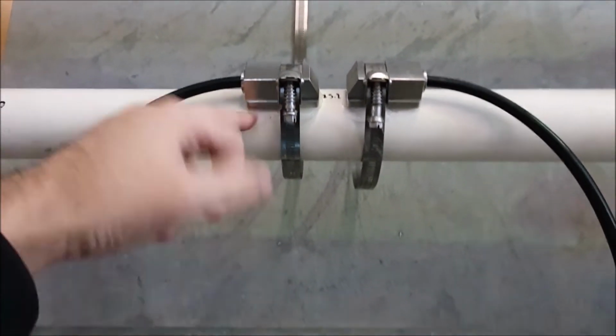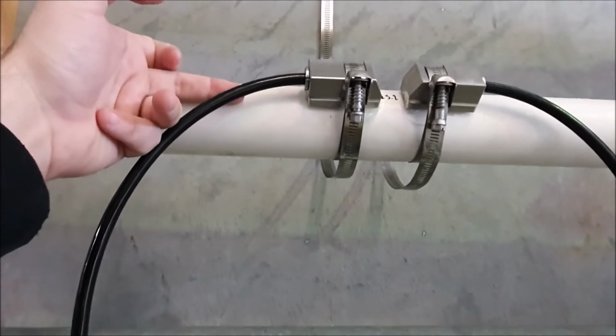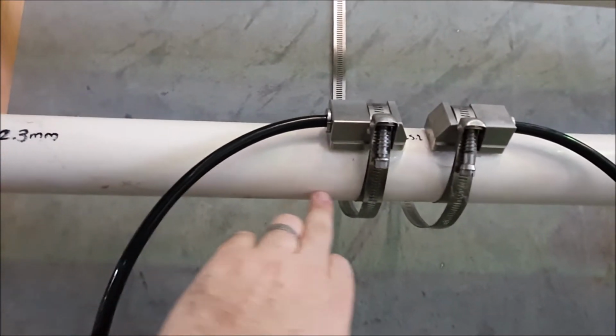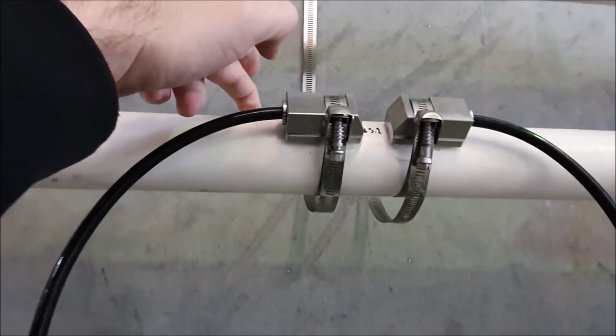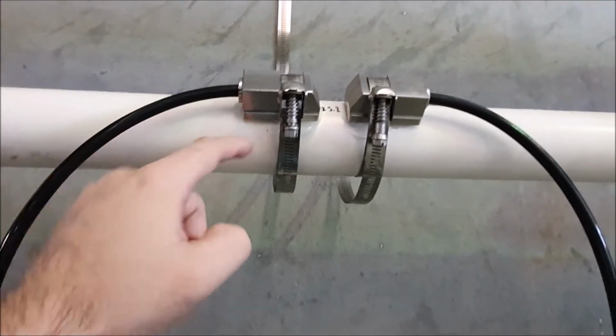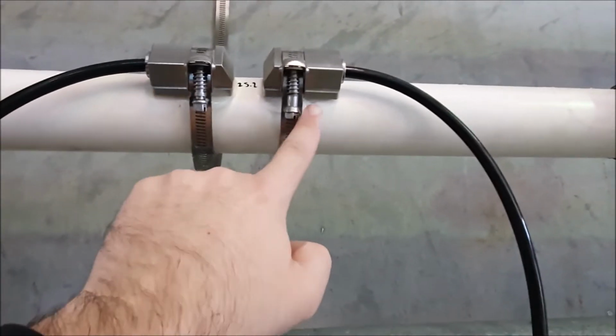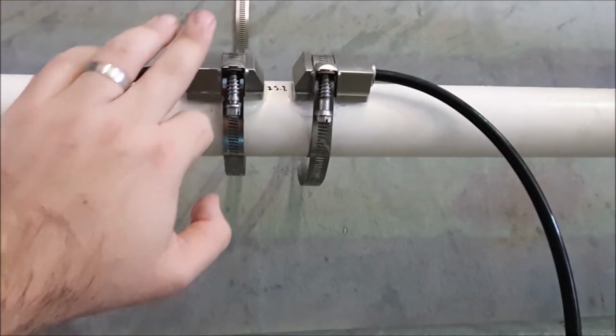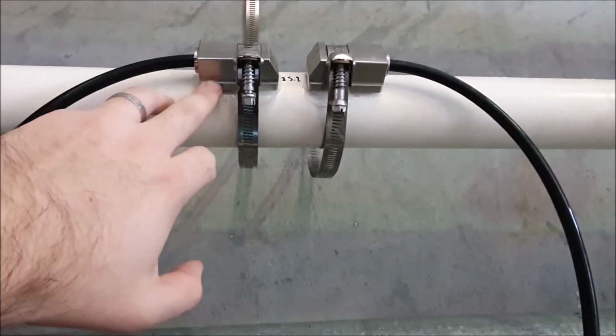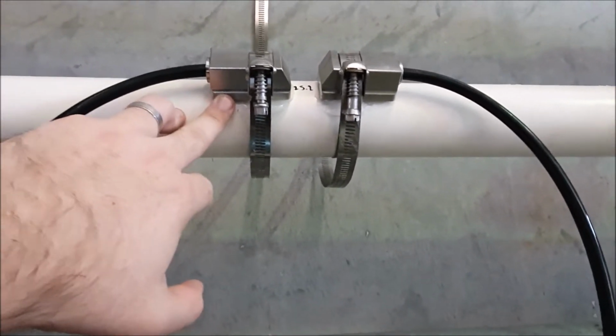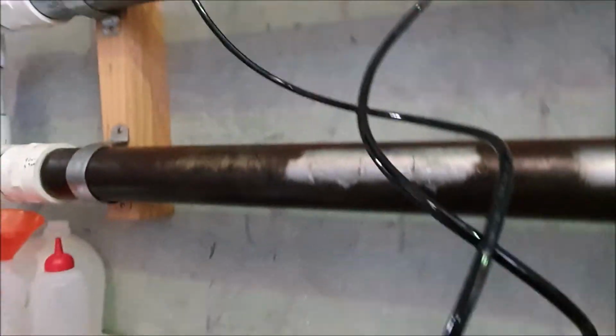Now you'll notice as well on the transducers we've got them mounted on the side of the pipe. At the bottom you might have some sediment, and in the top you might have some air. So if you have them on the side, the signal will bounce, avoiding both of those possible things that might be in your pipe, and this will give you the best signal without issue.